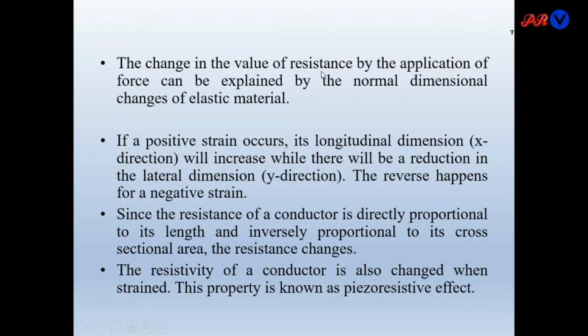The change in the value of resistance by the application of force can be explained by the normal dimensional change of the elastic material. So when force is applied, the elastic material dimension will change, and the resistance will change according to this dimensional change. If a positive strain occurs, positive strain means its longitudinal dimension in the x direction will increase, while there will be a reduction in the lateral dimension, meaning the y direction.